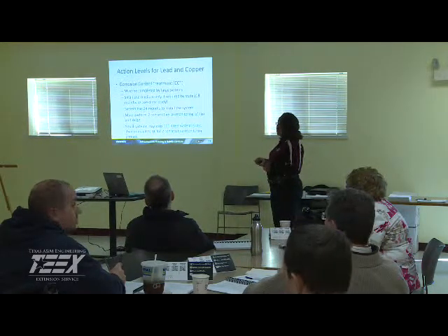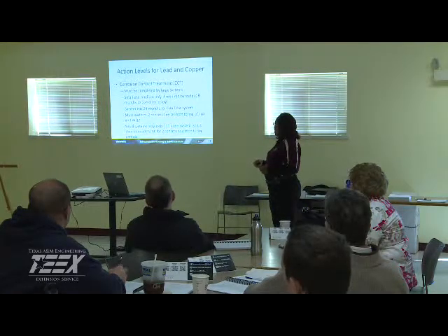So you go back to your primacy agency for direction for smaller systems. Systems then have 24 months to install, and must perform 2 consecutive 6-month monitoring periods of your taps and your WQPs. Small systems may stop the corrosion control treatment if they are less than or equal to the action level for 2 consecutive monitoring periods. So they give you that option.